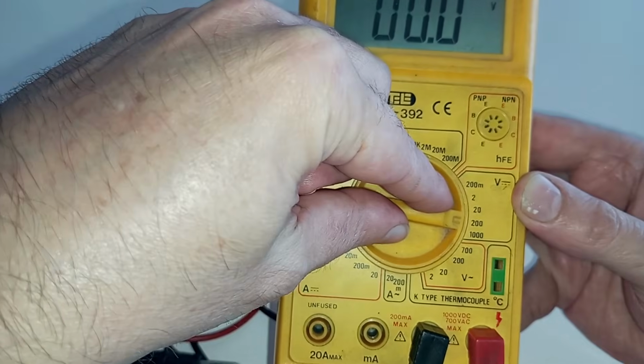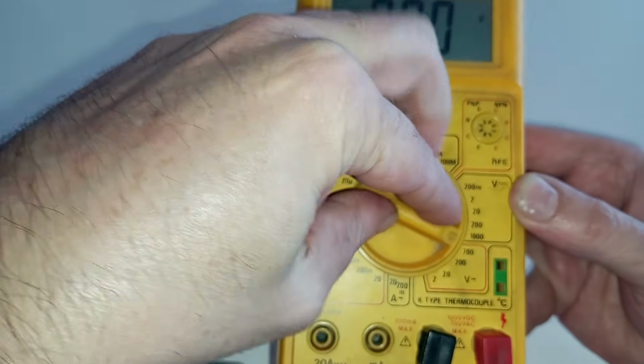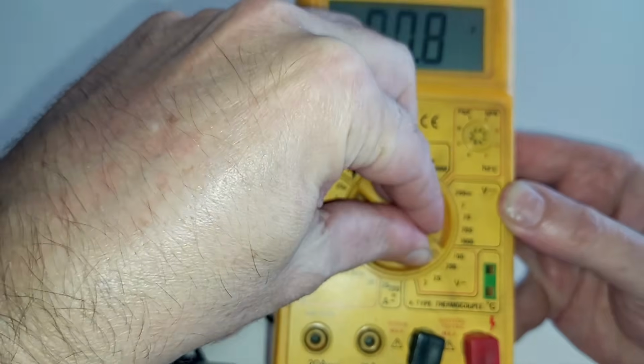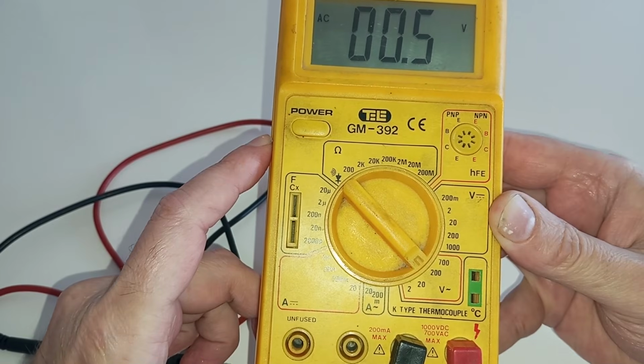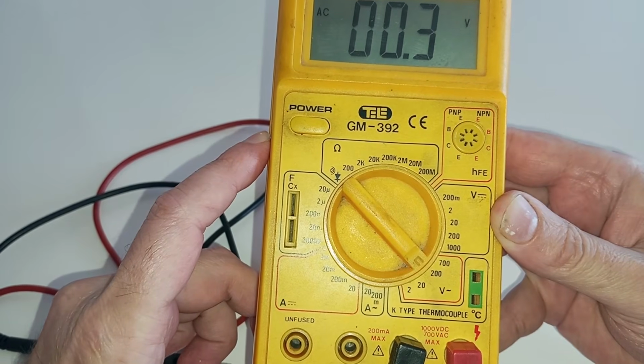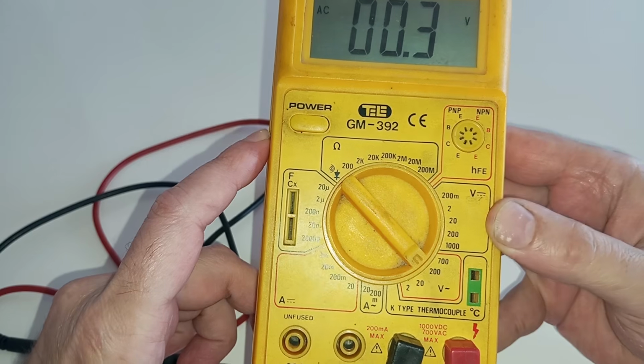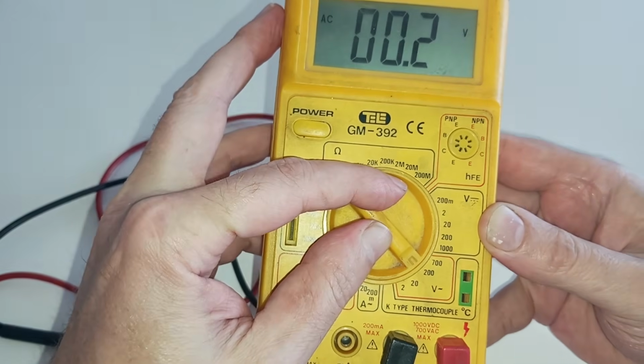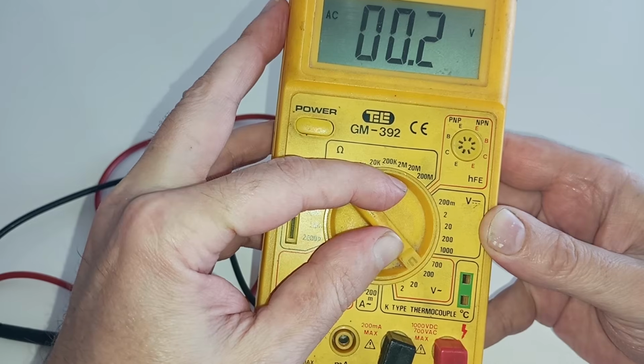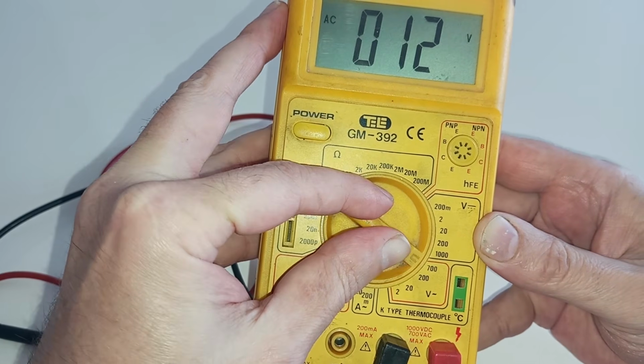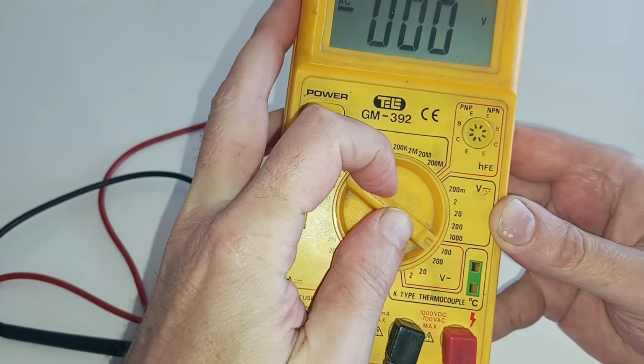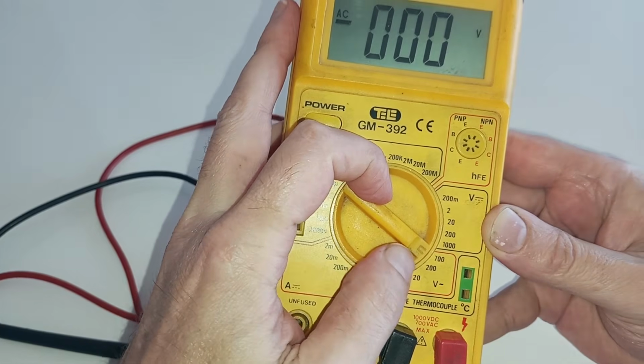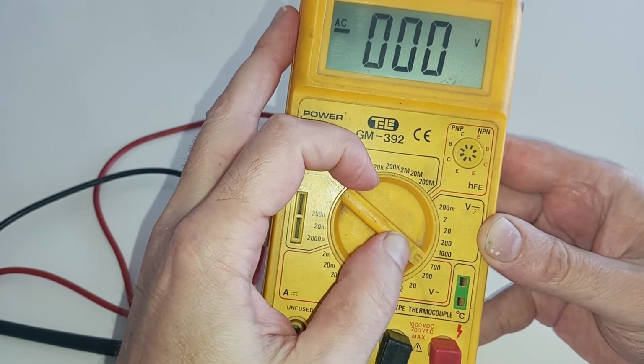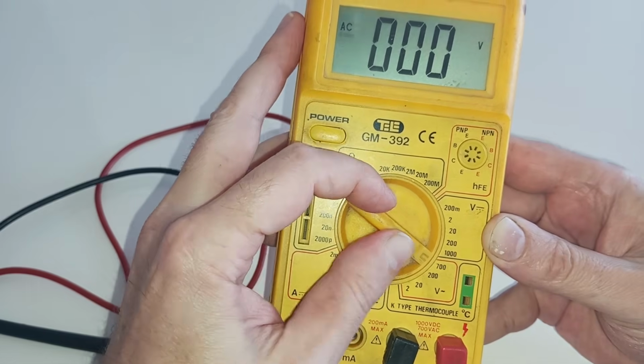Let's make another example for alternating current. Say you want to measure the voltage of your home installation, which in my country is 220 volts. In that case, I have settings for 200 and 700 volts. For 220, I will set it to 700 because 200 is too small. Always make sure the setting is bigger than the value you are measuring.